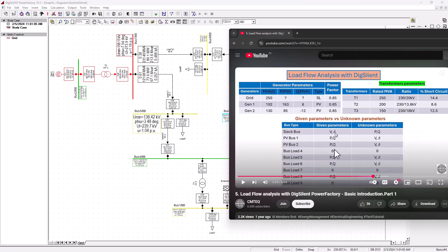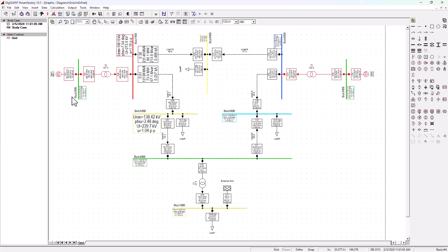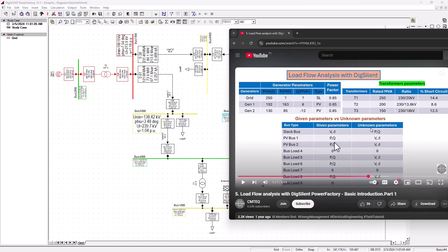The other confusion is that we listed the reactive power for the PV bus as a given parameter, whereas in a standard definition, the reactive power is unknown for PV buses. The generator's reactive power output is basically determined by the load flow analysis, and this is subject to its reactive power limits. This is why these parameters are not given — they are unknown parameters, and will be determined based on the system loading. But why did I specify Q as a given parameter for the PV bus? I did this for simplification, to basically help beginners focus on other aspects of the analysis.